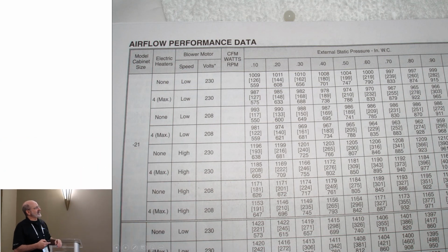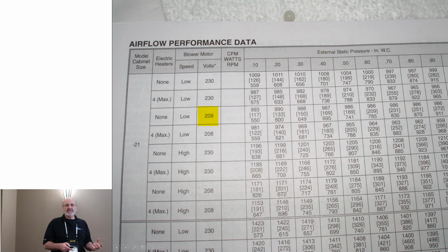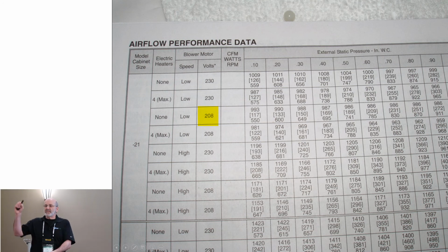I'm not sure why, but I'll show it to you for an ECM system. So this is actually taken in the field. You can kind of see the galvanized behind it. But again, we've got to pick the right type of equipment and the right configuration, because electric heaters could cause a little bit more static resistance. So we've got to match the way they did it in the lab. In the field, we matched up with electric heaters running at low speed at 208 volts, because that will affect things also. And we see a reading of 1/2 inch of water column on the manometer when we put the static pressure tips in to measure, and this would be the total external static pressure.